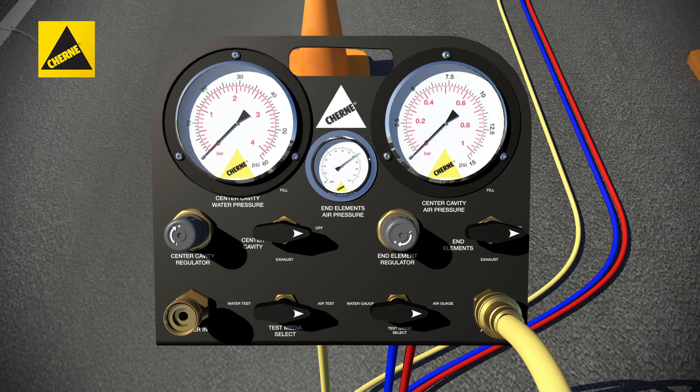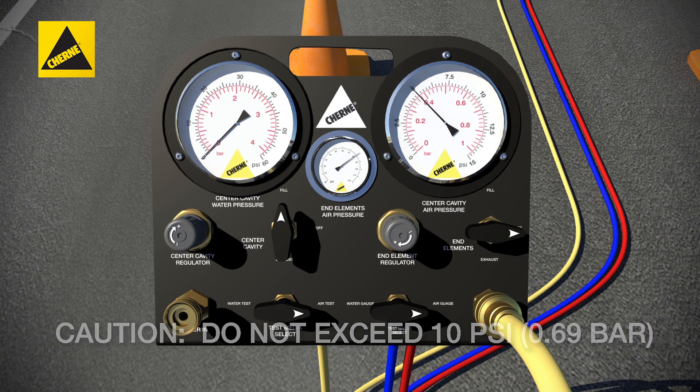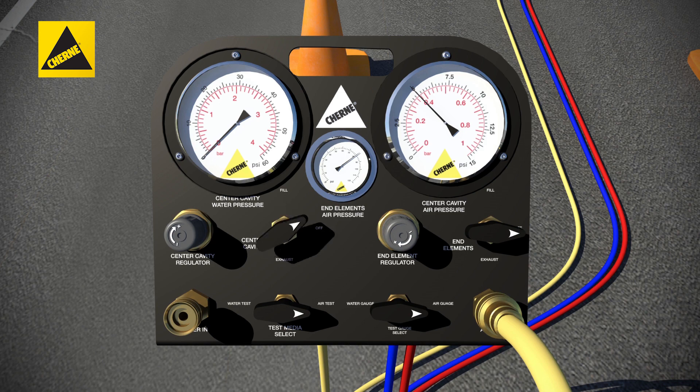To pressurize, place the test pressure inflation valve in the fill position. Turn the test pressure regulator until the specified test pressure is indicated on the test pressure gauge. Place the test pressure three-way valve in the off position.